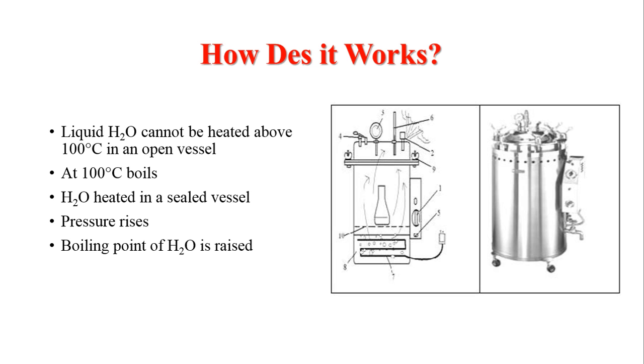How does it work? The autoclave is a steel chamber filled with water. The water boils at 100°C and starts producing steam. When we close the chamber, the steam builds up pressure. This high-temperature, high-pressure steam can penetrate into cells as well as spores and denature the proteins inside them.